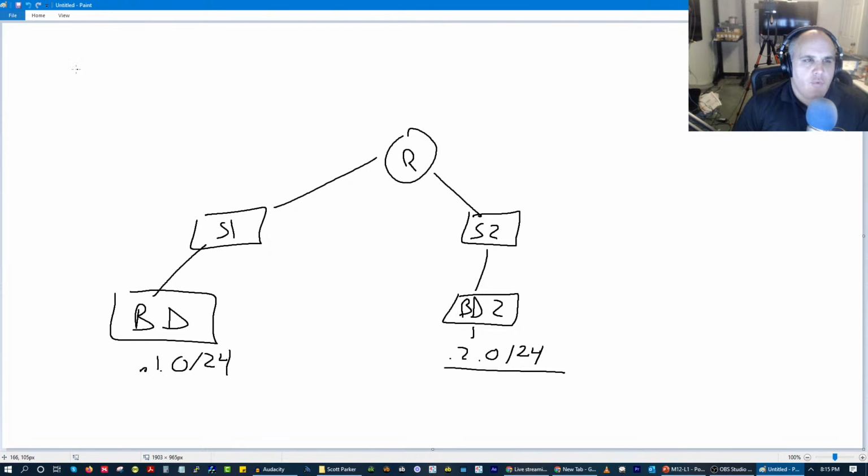Now, how BACnet works is it uses 2 broadcast services, and then the rest of its services are primarily unicast and multicast, meaning they're one-to-one or one-to-many, whereas broadcast is one-to-all. So in order for us to do our 2 broadcast services, which would be the who is, I am, and the who has, so we're just going to put who and has.